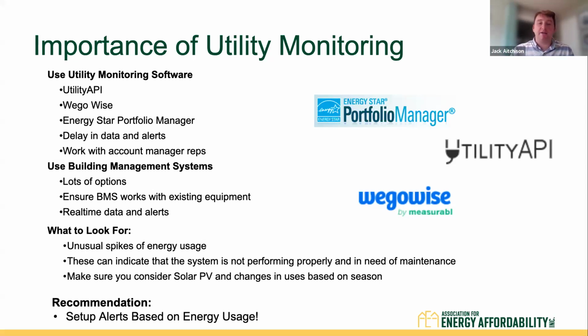However, the drawback of using utility monitoring is it's going to be at least 30 days since the issue started occurring before you see the issue and know to react. So that's where building management systems have a leg up, where they can give you real-time data. There's lots of options for building management systems, and I know this is what Mark is going to talk about. Ensure the BMS works with existing equipment, and then you get real-time data and alerts. What to look for: unusual spikes of energy usage.